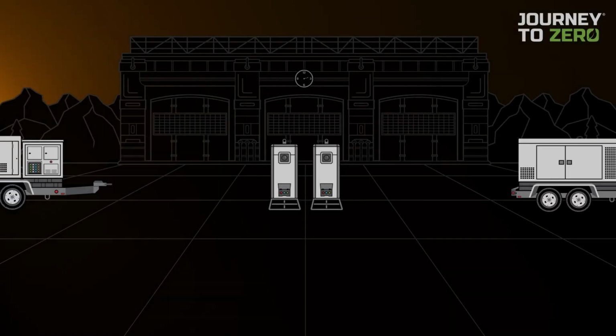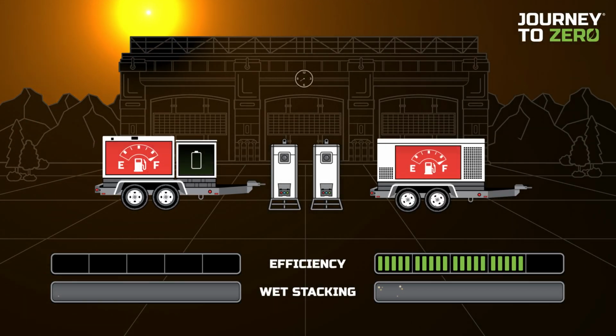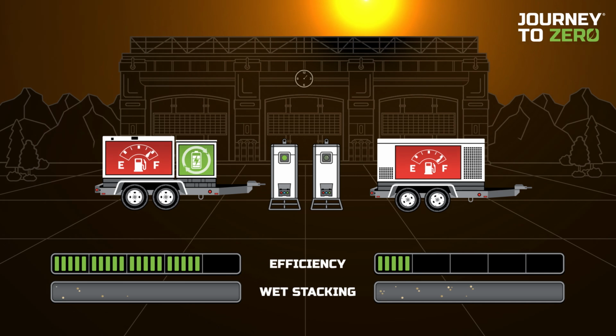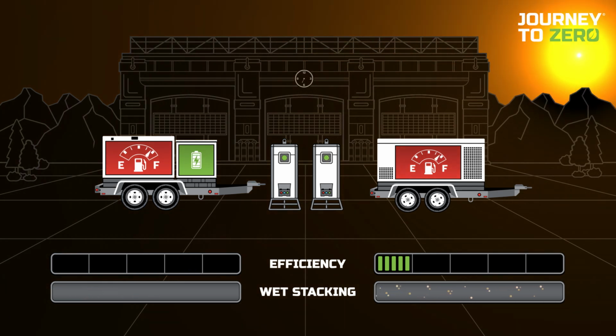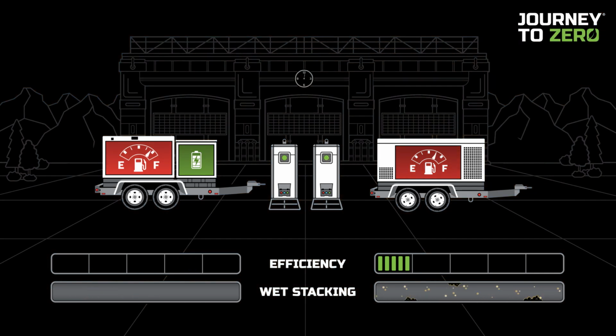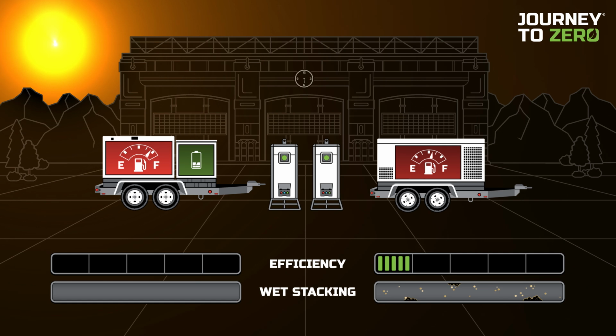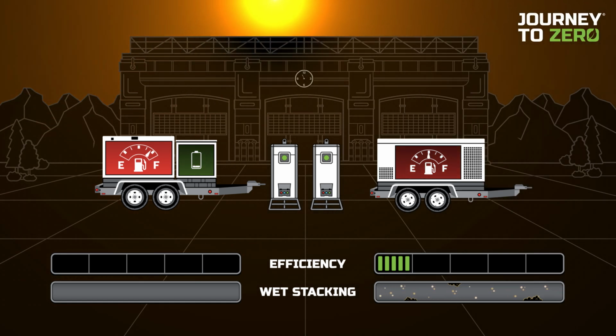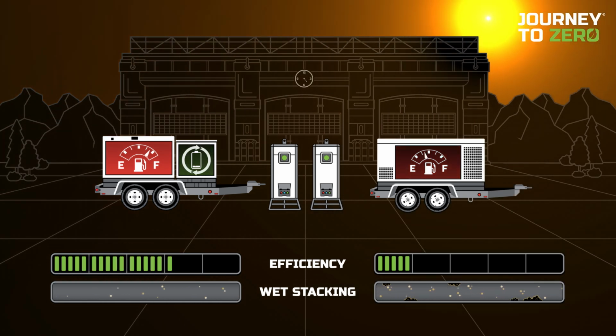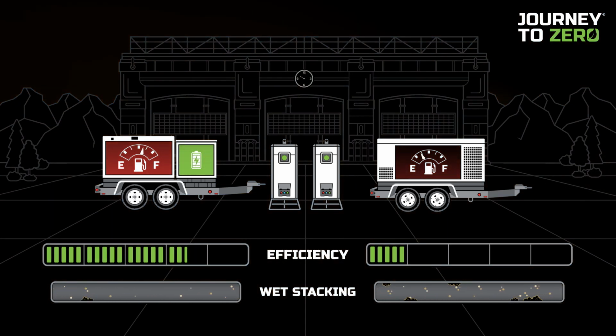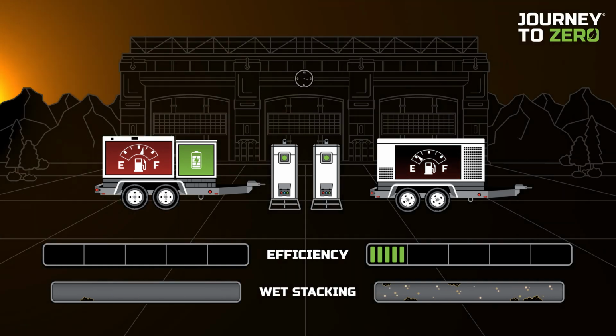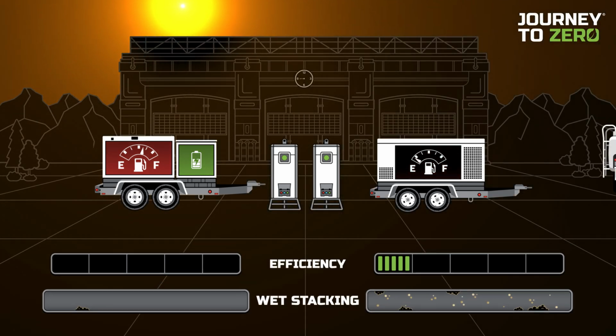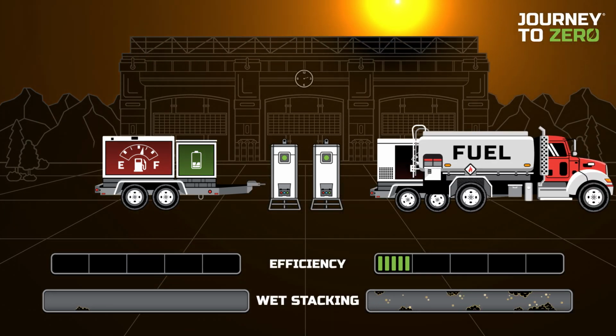A traditional diesel generator is sized to handle peak loads during equipment startup, which often results in it being oversized for continuous loads. In typical applications, the generator operates at around 10% of its rated capacity, leading to light loading on the engine. Operating at low loads prevents the engine from reaching peak efficiency and optimal temperatures, causing unburned fuel to pass through the exhaust.